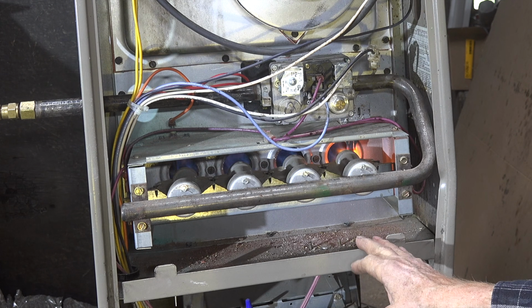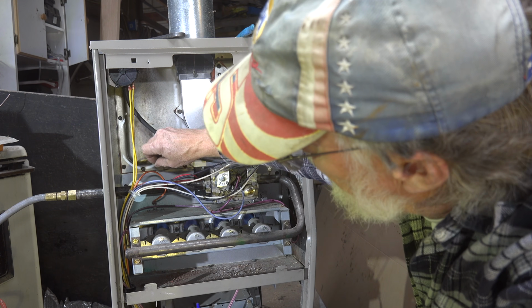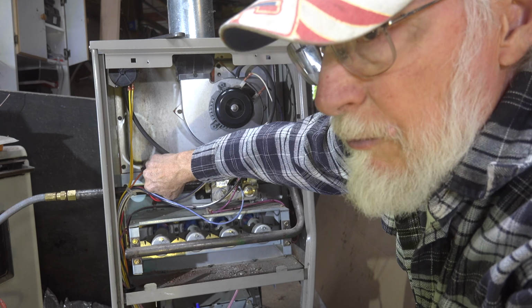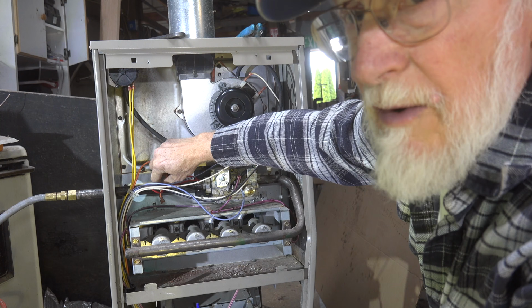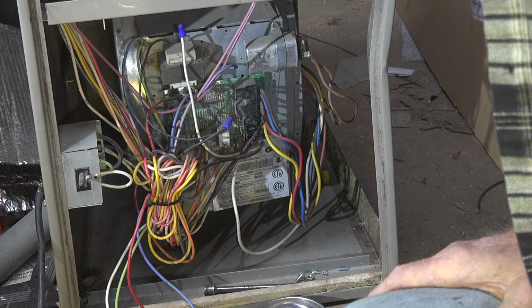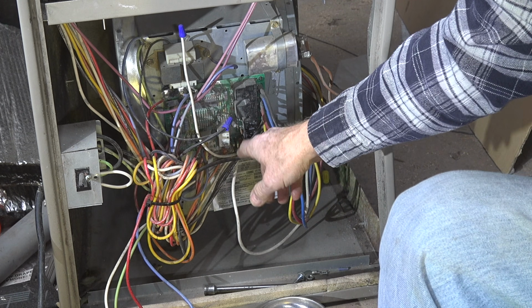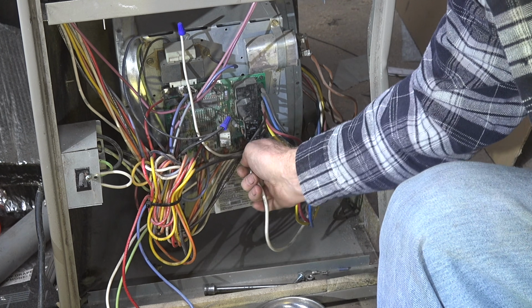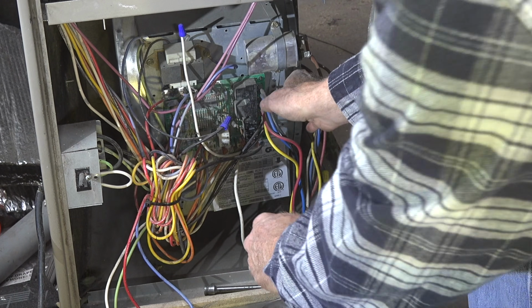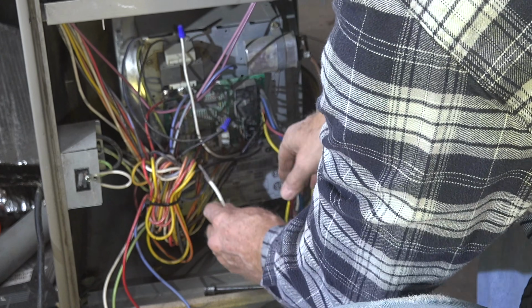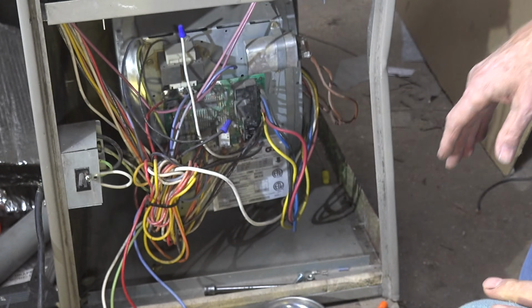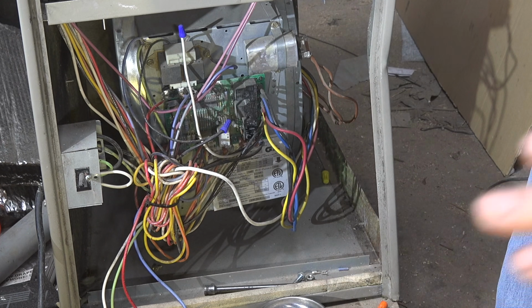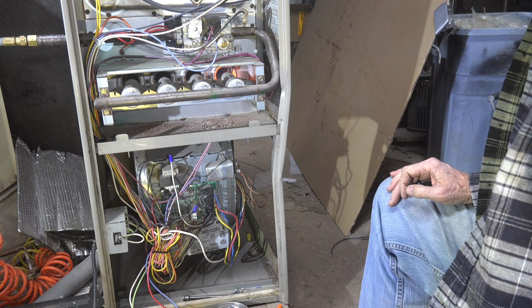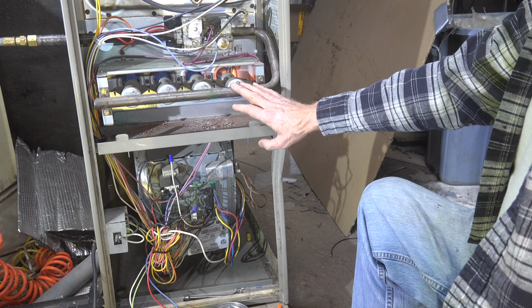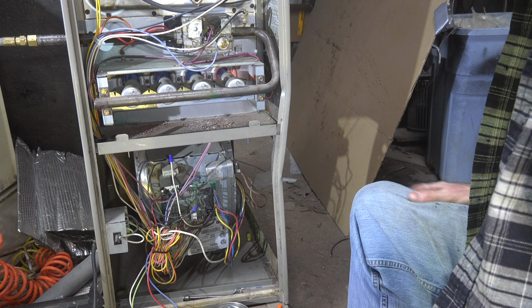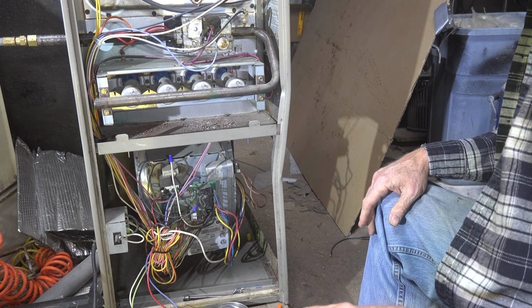Okay, once this thing is going, I would be checking the flame rod. Pull the wire off the flame rod. Should shut off within about a half a second, which it did. One other thing I would do, I would go down here, again using your camera, I would pull off the white wire from the fan. This is with the power off. Pull it off, put it someplace where it's not going to short, and fire this thing off. Okay, the burners are running, but the fan is not going to come on because I pulled that wire off.